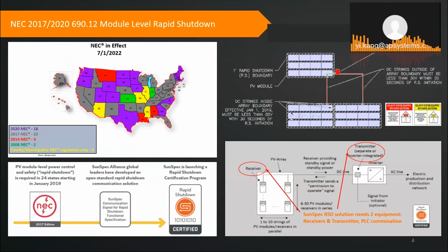So under their requirement, you can see there are two pieces of equipment. One on the module side, they call it the receiver, which is on the back side of the PV panel, receiving the signal, and the function of that receiver is to cut the power from the PV module. The other equipment, they call the transmitter, is the signal generator. It generates the PLC, power line communication, signal through the DC line.